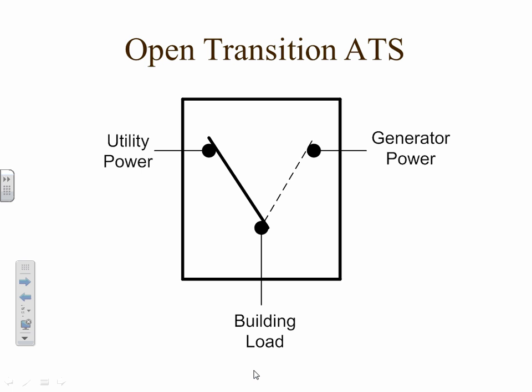And that works fine until the power comes back on. If he hasn't switched his main off to keep it contained, the generator backfeeds into that box, and he's in trouble. So a transfer switch will safely disconnect. If you look at this drawing, when this thing operates, it's going to move this arm from here over to this position, totally leaving just a dot there as far as the drawing is concerned for utility power. So if utility power comes back, that's all the further it's going, to the contacts. And the generator set is feeding the load fat, dumb, and happy.